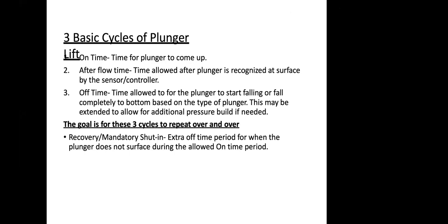But what you're doing during that on time is you're waiting for the plunger to come up. You actually have the controller in an open state, the pneumatic valve is open, allowing the well to flow, and your controller and the firmware inside the controller knows to be looking for a plunger. It knows to be looking for that sensor to see that plunger. So this is the time allowed for that plunger to come up, this open time.